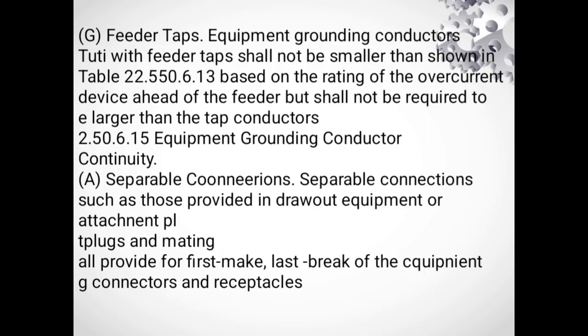A. Separable connections, such as those provided in draw-out equipment or attachment plugs and mating connectors and receptacles, shall provide for first make, last break of the equipment grounding conductor. Metal parts of electrical equipment, motors, appliances, etc. that could become energized need to be grounded for safety. This applies in wet areas, near metal, or in hazardous locations. Cord and plug connections often need grounding too. Grounding can be done with wires, metal conduit, or special cable.